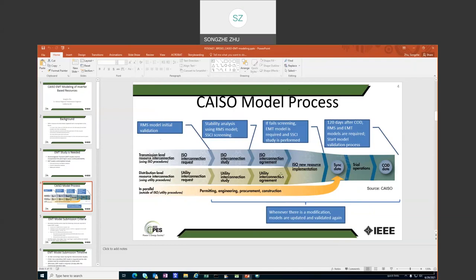Of course, during this entire process, the owner will make multiple changes. They could change everything from the inverter to all the interconnection facilities, and maybe not just one time, many times. Every time they make a modification, if the modification is approved, the models must be updated and validated again. The modification is not just during the interconnection process. It could also happen post commercial operation. We do allow post-operation modification as long as it's non-material, but that will require an update of the model, and we will revalidate all the models.